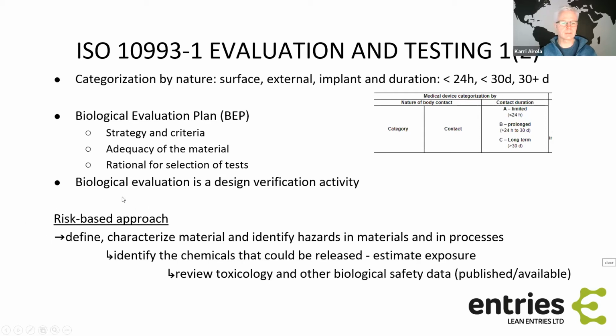And here is once more mentioned the risk-based approach: first define and characterize your material and identify hazards, and then identify the chemicals that could be released and estimate the exposure times to the patients, and also the chemicals that could come from the processing stages. Processing stages, if they are in contact with some processing instruments, or degradation products, for example, if you are applying some irradiation and there will be some degradation of the polymers. So these side products and unintended degradation products you should take into account in these estimates and assessments as well.